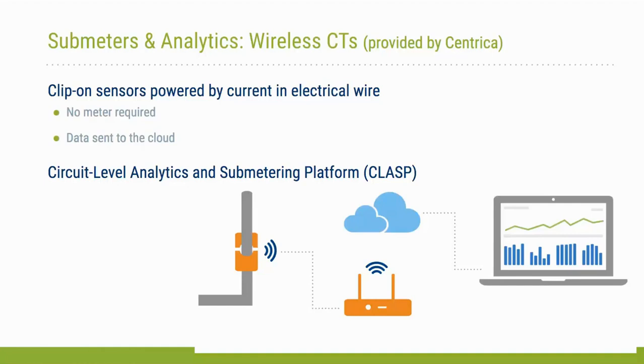Let me describe the topology of this type of submetering technology. As I mentioned before, they're clip-on sensors, so they're also very easy to install — some of them don't even require tools. However, we have to open the panel to actually get the cables connected to the breakers. As I mentioned, there's no meter required; they're really gathering current information and not voltage — they're not measuring voltage in this case. But just to describe how this works: they are self-powered meters that need some current going through the wire they're metering in order to provide measurements.